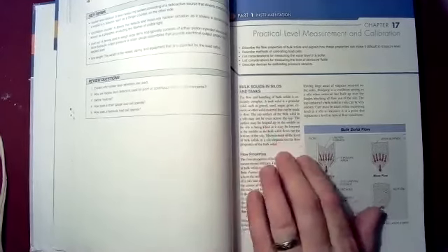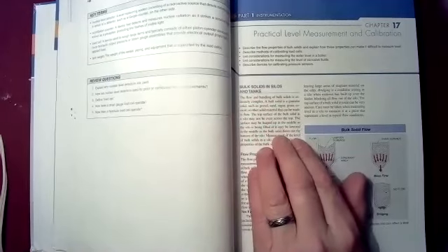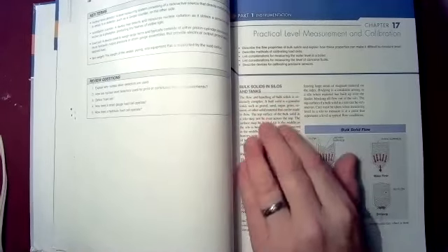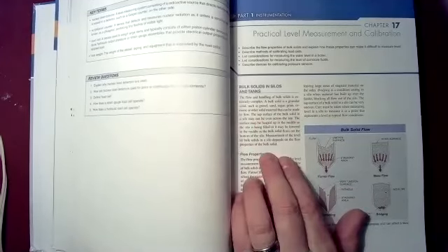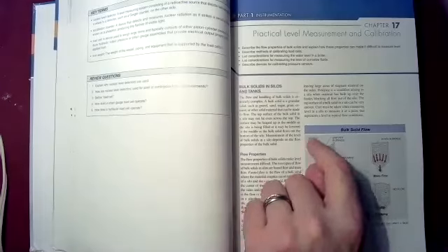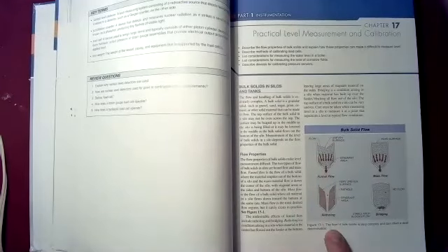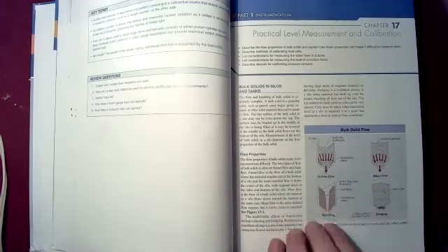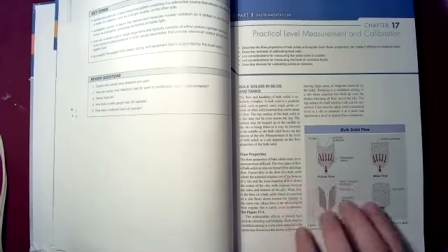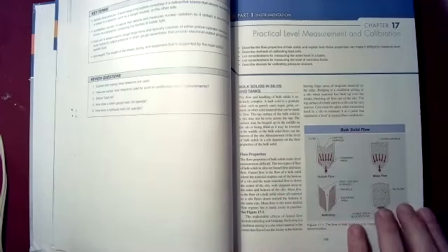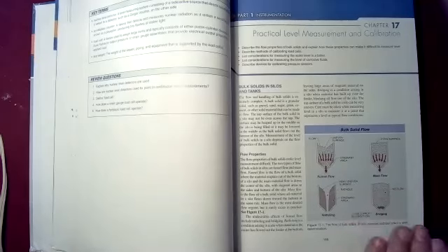Obviously, if anybody's ever looked down inside of a silo, you know that the material that you drop down inside of a silo can be heaped up, and when you start emptying it out from the bottom of the silo, you get a big uneven surface. You might even get something called rat holing or bridging, and all these things can make your level measurements really, really hard and inaccurate. So as you do any of these measurement systems, you have to think about what the end effect is in terms of level.